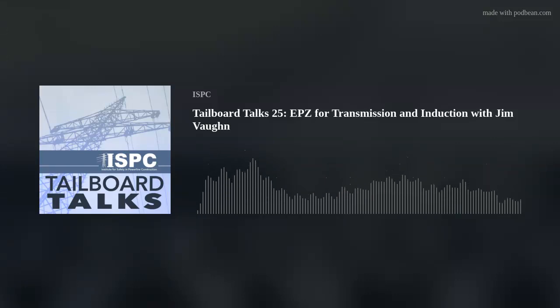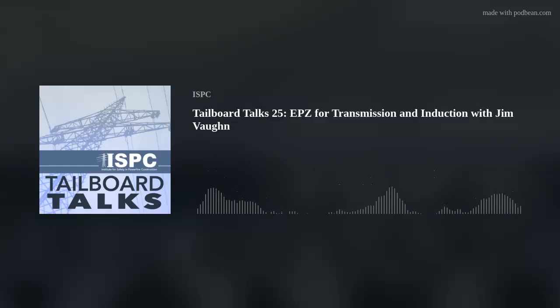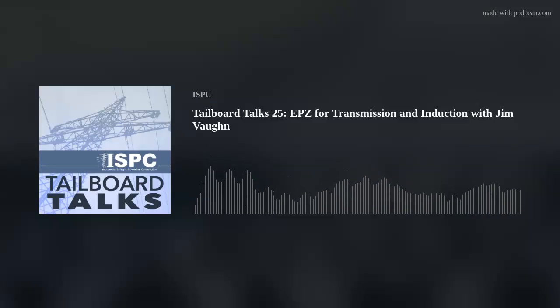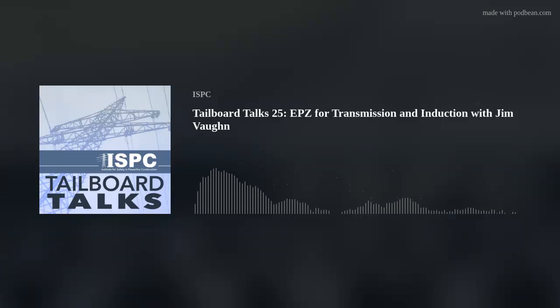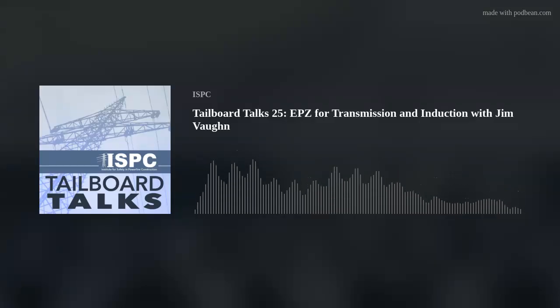Then you connect to the nearest phase with a hot stick. You ground in order of the closest phase first. And then you disconnect in reverse order. And then you always use a hot stick. And the last one, number 6, is never handle the unconnected end of a connected ground cable. Doesn't matter what it's connected to, never handle the unconnected end, with the exception of the ground electrode connection that's isolated from all other sources. You could do that. So our cardinal rules: 1, make the ground electrode connection first. 2, connect to the closest phase first with a hot stick. 3, ground in order of closest phase first. 4, disconnect in reverse order.